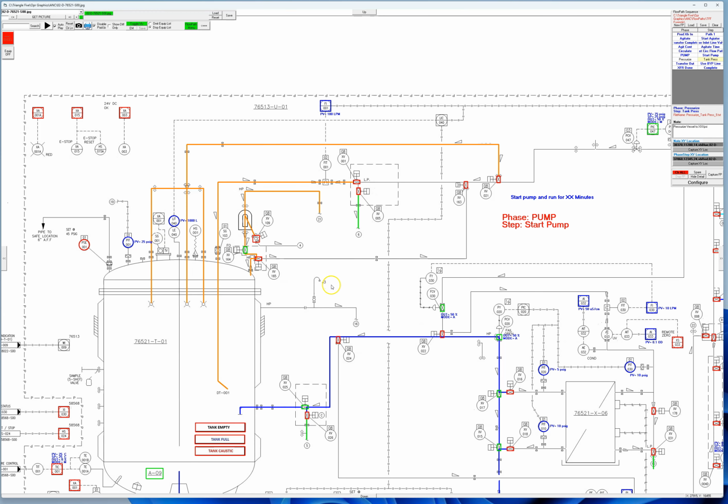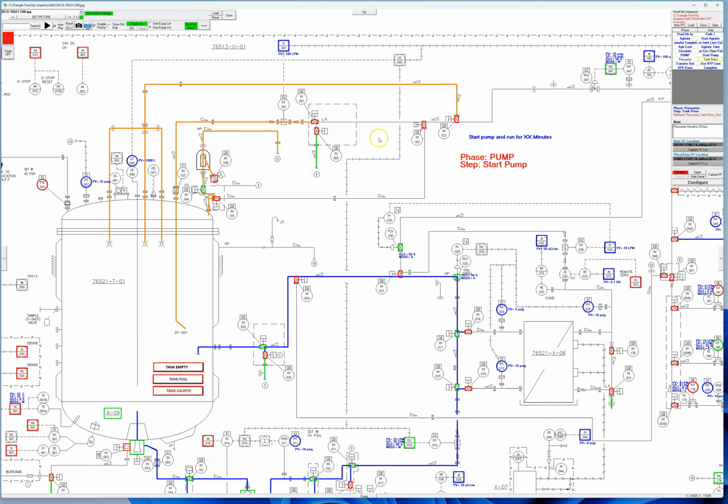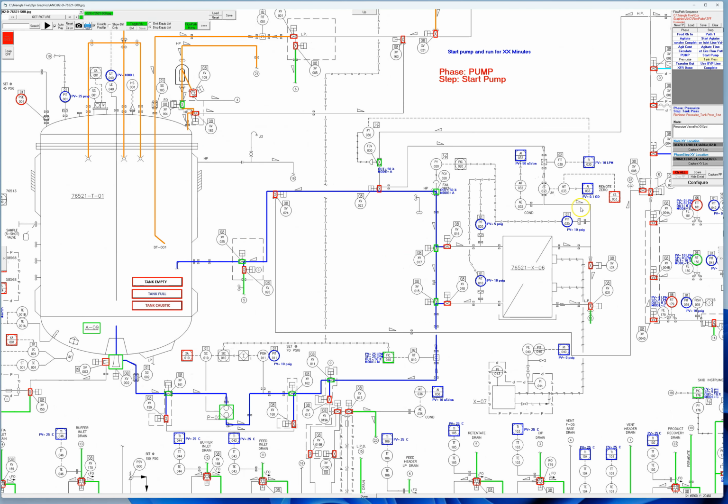So the reason this is done is during air blow, we may introduce pressurized air into the vessel, and we may, in the air blow, blow through here and drain. That was one of the criteria that was implemented for this TFF. So that's what that means. We pressurize it, and this line here is basically being pressurized as indicated. So we pressurize that, and then we hit capture.